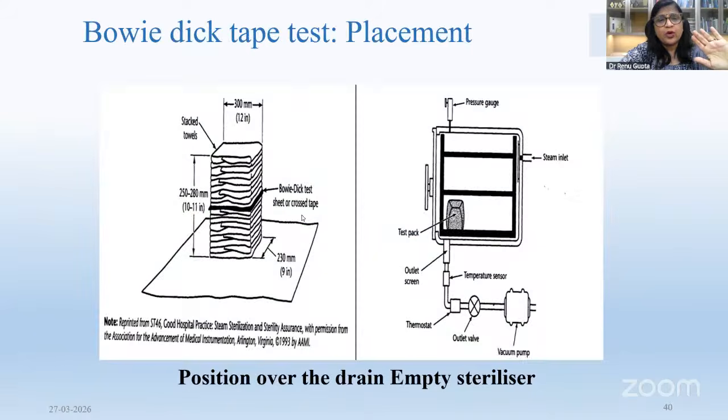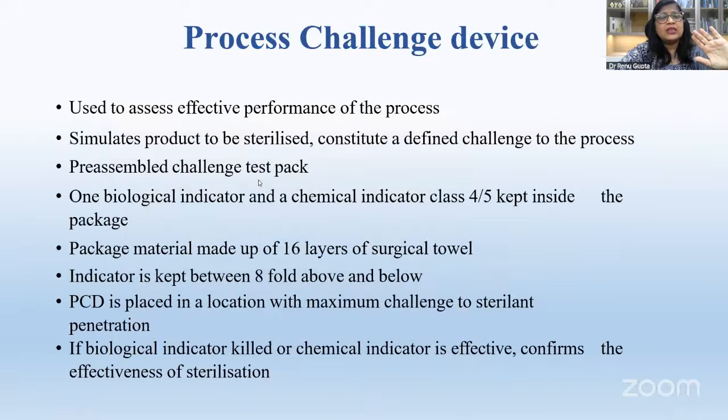So this is called a process challenge device, which I showed you. In this, it helps how to put it. You cannot keep this Bowie-Dick tape test like this on the drain. You have to pack it because you have to check for the complete load.